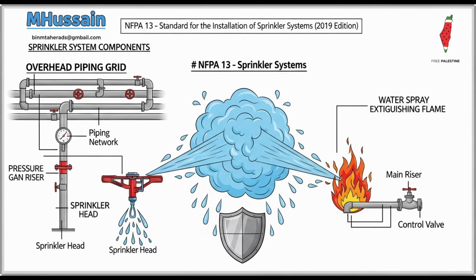Okay, so what does that plan look like in practice? What are the options? The options are practical, but they can be costly. You could install pipe that's resistant to MIC, like CPVC, which is mentioned in Annex A, that's a non-metallic option. Or you could treat the water supply with an approved bacterial inhibitor. Or maybe set up a corrosion monitoring station where system components can be physically checked at set intervals. The core idea here is really preventative maintenance against that internal decay that traditional system flushing just won't fix.